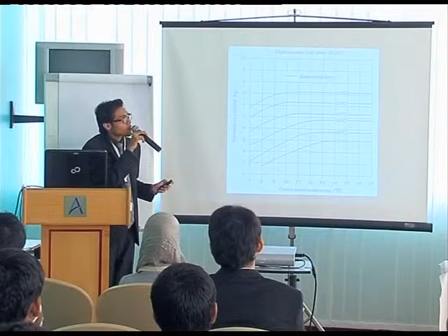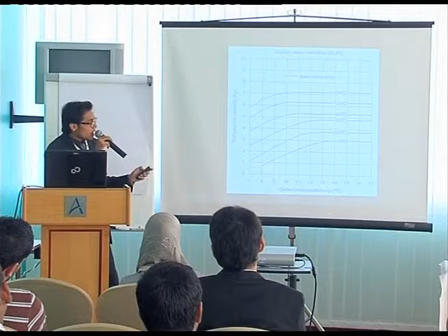Now here, as you observe carefully, our generator temperature is around 88 degrees centigrade, somewhere here, or 85. And our required target for the chilled water storage tank is 9 degrees centigrade. That is, we want to achieve that temperature. So if we intersect the line, our efficiency is around 0.5 or below 0.5. So for this system, the refrigeration capacity is below 5 or 4, somewhere in between, in kilowatts. That again proves that the refrigeration capacity which we have considered coincides with our data.